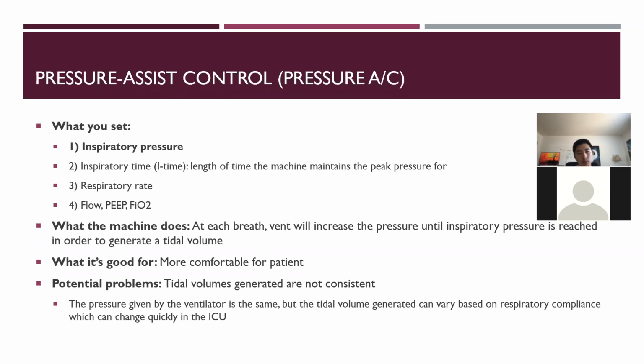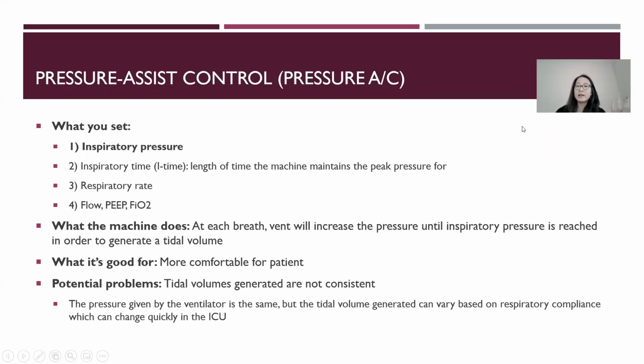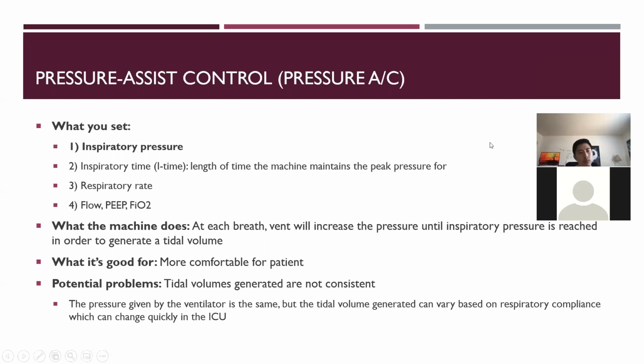And again, I'll show this on a graph on the next slide, but what it's good for is that it's a little bit more comfortable for the patient, which I'll show with the flow graphs. And also, if they're not doing well on volume control, you can try switching over to pressure, see if they do a little better with that, if they're more comfortable. So potential problems, obviously, one of them is that you are no longer in control of the tidal volume. And this can vary based on the respiratory compliance, which can change pretty quickly in the ICU. For example, if someone gets a pneumo, or if they're slowly building up an effusion, these are all things that are going to change the compliance and affect your tidal volume to the point where they may not be getting enough air.